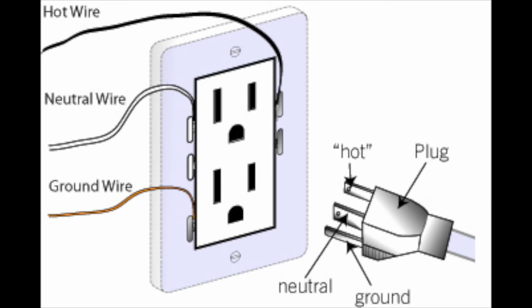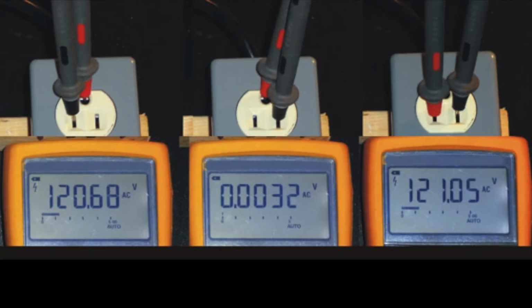So in the US, we typically have electrical systems set up with a neutral, hot, and a ground. Now, what a lot of people don't realize is that the neutral and the ground are connected. So practically speaking, if you take a voltmeter and measure between the hot and the ground, you're going to measure approximately 120 volts. And if you measure between the ground and the neutral, you should get a negligible voltage, usually in the millivolts range. And if you measure between the hot and the neutral, you should get around 120 volts.